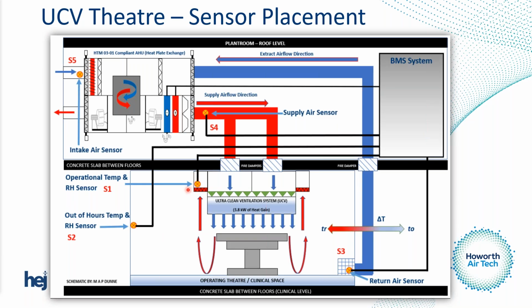If we have a stat there, then the offset within the BMS system is much lower, and will give you a much more accurate reading. You can see we have a standard air handling unit, and the ductwork comes up through in this fashion. As I mentioned before, 33% of the air delivered to that 500 air changes comes from the HVAC system, and we have the recirc 66% moving around in this fashion 500 times an hour, and then from the air handling unit we look for 22 air changes an hour.